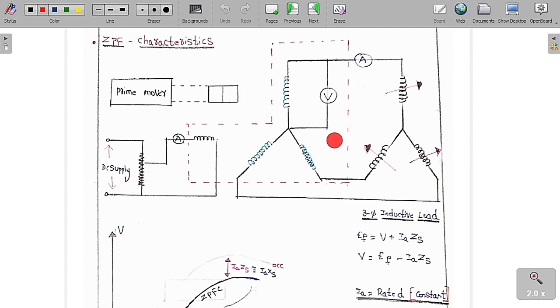And here it is a star connected armature coil present on the stator. This voltmeter measures the per phase voltage, and this ammeter measures the armature current. Now we have to keep a load which is purely inductive, because it is a zero power factor characteristics test, meaning the load should be purely inductive, so the power factor of the load is zero. So it's a three-phase inductive load.